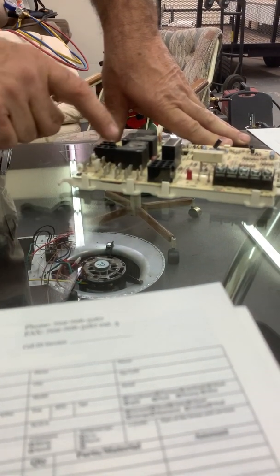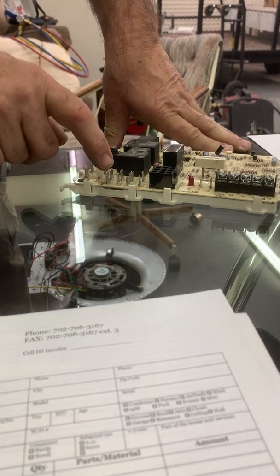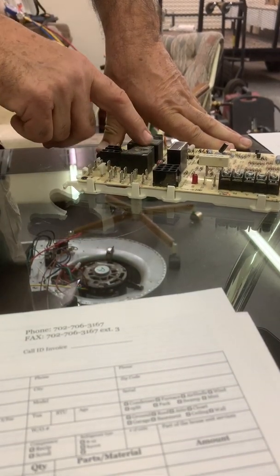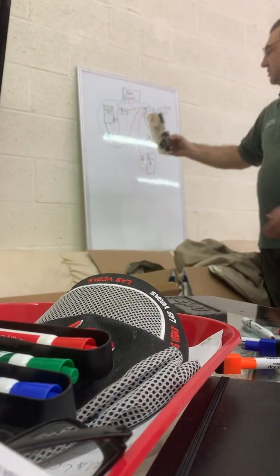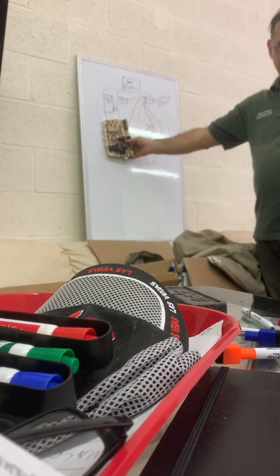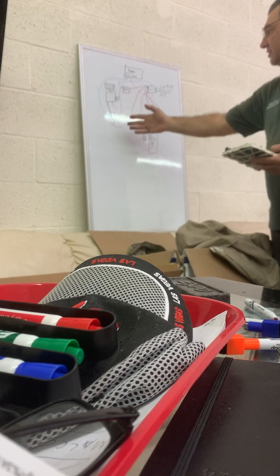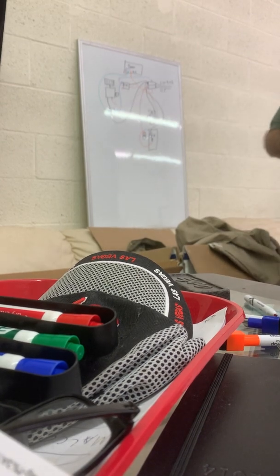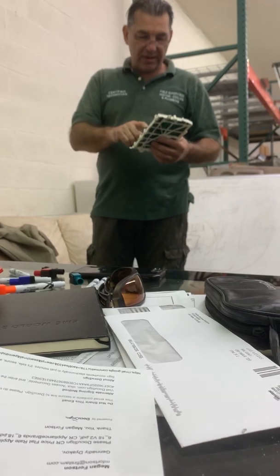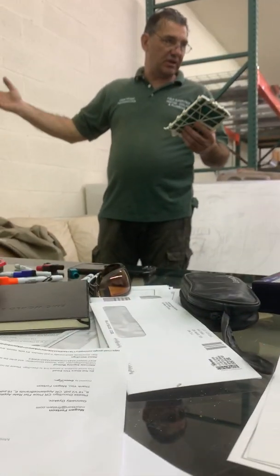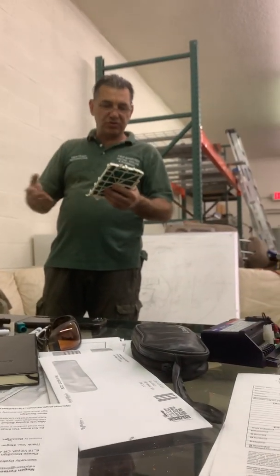On the heat side, why is there a separate plug? Because on the heat side, there always has to be a time delay. So this supplements some of these parts, meaning you wouldn't need those parts separately. On the cool side, that's the only thing it controls, just the contactor and the blower motor. On the heat side, there's more to it, you have limit switches, the inducer motor, gas valve, and it all goes through here.